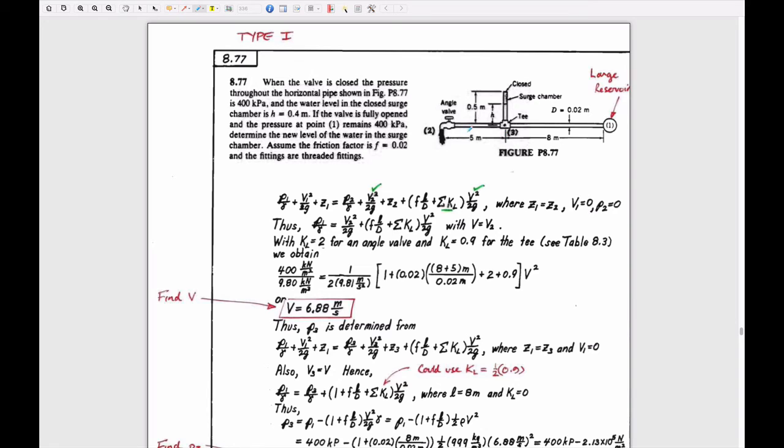And so actually this is a bit like a hydroelectric dam. If you think about this, instead of being horizontal, being inclined, upstream lake, downstream effluent from the turbines, then typical hydroelectric plants not only have a tunnel coming down, but they have what's called a surge shaft, which is a vertical shaft either open to the surface or just filled with air, so that when you close the valves off down in the generator hole, and you do it in a hurry, all the momentum of this water coming downhill, which has a lot of momentum, mass times velocity, that you want to shut off just like that, instead of hitting the gates and blowing the gates out and kicking them into the turbines themselves, it actually has somewhere to go by taking the momentum and pushing it up this surge chamber.